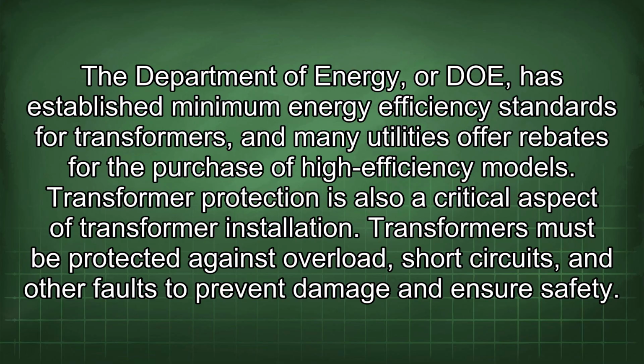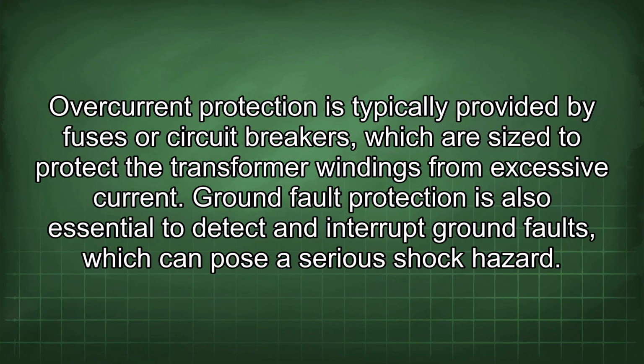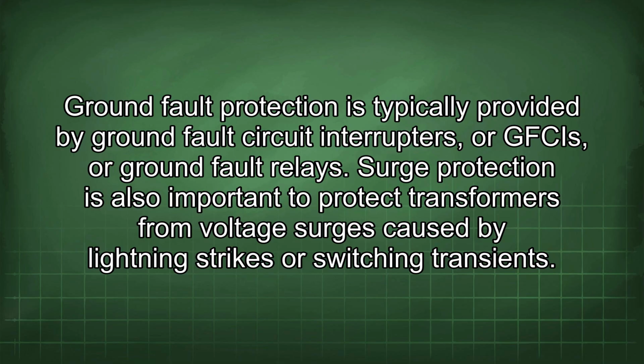Transformer protection is also a critical aspect of transformer installation. Transformers must be protected against overload, short circuits, and other faults to prevent damage and ensure safety. Overcurrent protection is typically provided by fuses or circuit breakers, which are sized to protect the transformer windings from excessive current. Ground fault protection is also essential to detect and interrupt ground faults, which can pose a serious shock hazard. Ground fault protection is typically provided by ground fault circuit interrupters, or GFCIs, or ground fault relays.